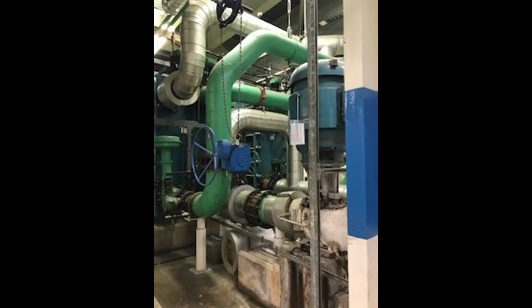Stator cooling water pumps is also tied to the turbine, so the stator is part of the generator. And we need to keep the hydrogen in the generator cool. Here we have some chain-operated valves. They're quite common in older plants. You know, they would be a bit too high or complicated to get to with a ladder, so we would chain-operate them. As a smaller woman, when I started my career, I found it very hard to operate these valves. So what I would do is I would stand like on the pump beside it, jump, grab the chain, and use my body weight to close the valve, and hope no one was watching, basically.